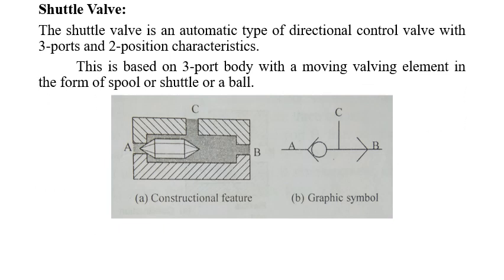The shuttle valve is an automatic type of direction control valve with three ports and two-position characteristics — it has only two-position operation but three ports. It is based on a three-port body with a moving valve element in the form of a spool, shuttle, or poppet. Ports A and B are the pressure/air supply ports; depending on which side has higher pressure, it will close the opposite side port. Port C is always the output port. If equal pressure is supplied to both sides simultaneously, the output is still obtained.